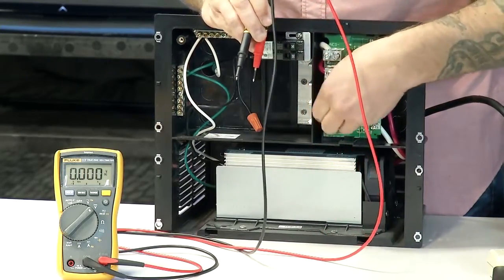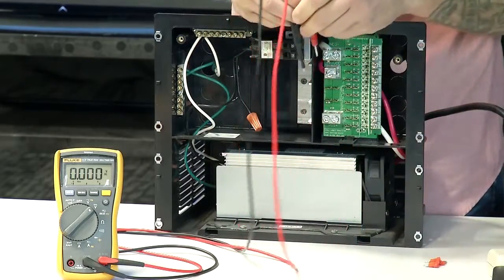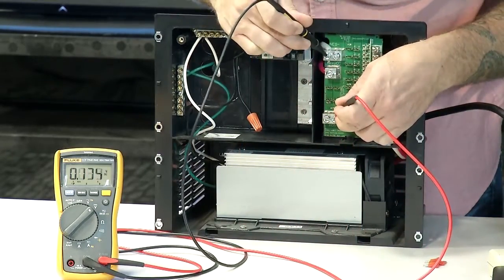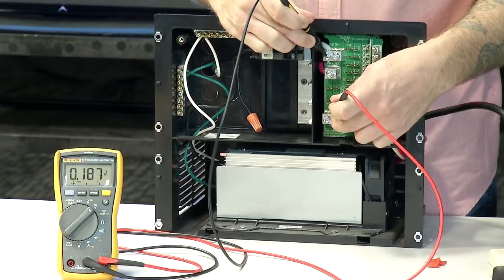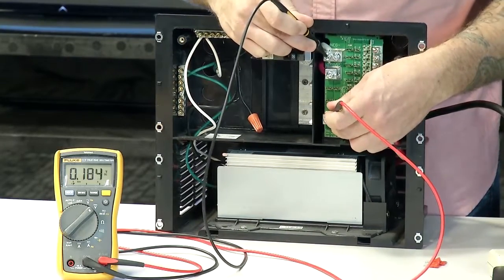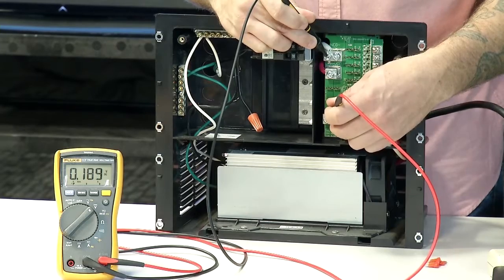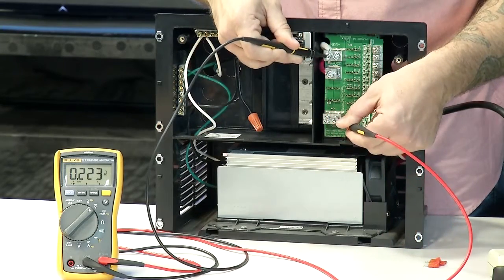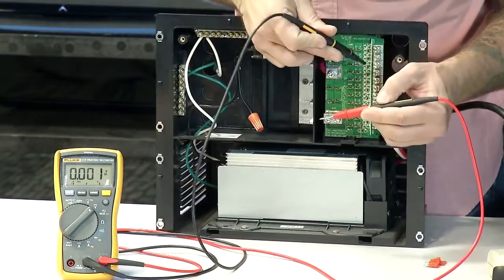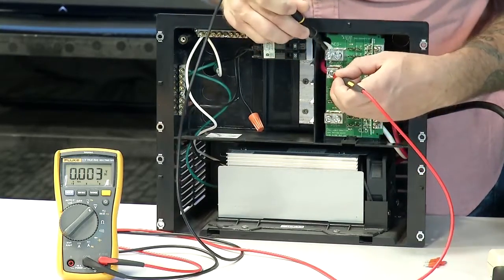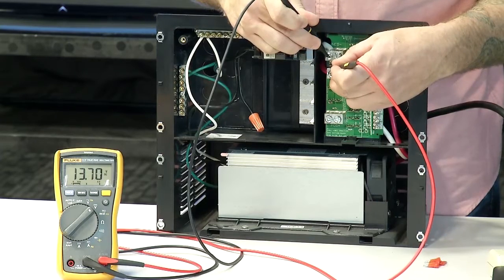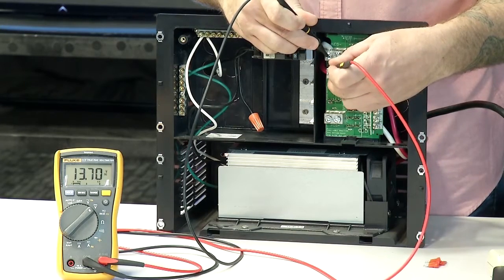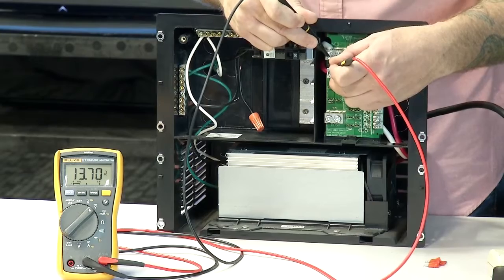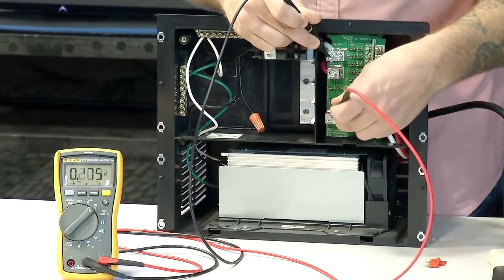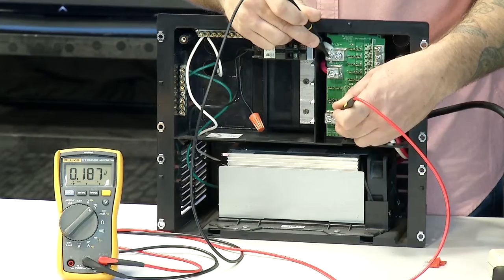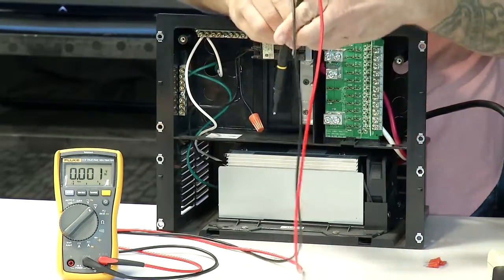If I was to pull these two fuses and now check that same spot, you'll see I have no voltage. What that is indicating, say those fuses are blown. So if those fuses were blown, you'd actually be getting nothing at your battery cables and nothing at your DC fuses. But you measure back at the converter input, and your converter is still working. So if you're reading good voltage at your converter coming in, but nothing coming out to your battery or your 12 volt appliances, you need to check those two 40 amp fuses that I just pulled out.